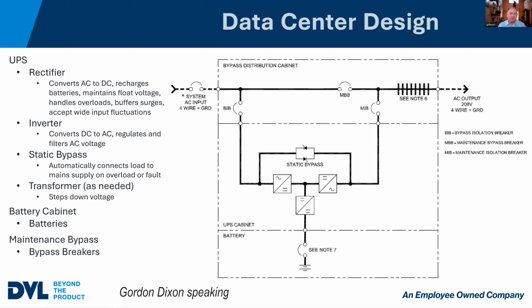So it's really important that you determine how much time do I need. If you've got a generator on site and it's going to come in and accept a load in 15 seconds, then you only need a minimal amount of backup time on a UPS. Now, just so you know, and you're not surprised when you ask for it, there aren't any UPSs out there that provide, at least at the large 3-phase, 1 minute of backup time. It's just got to do with the transfer of load, right? When you're going with large electrical loads like that, you can't really carry a small amount for a small time. So generally speaking, a UPS, the minimum is going to be 3 to 5 minutes.